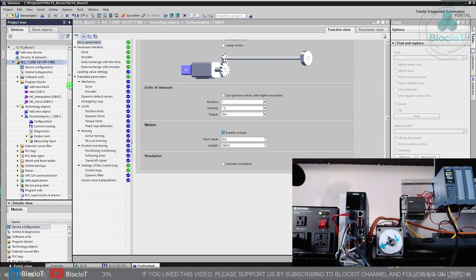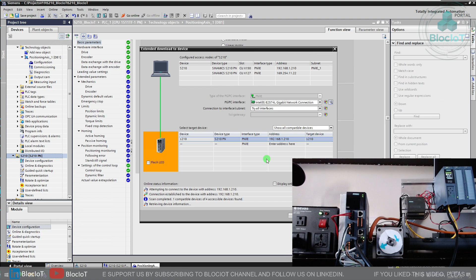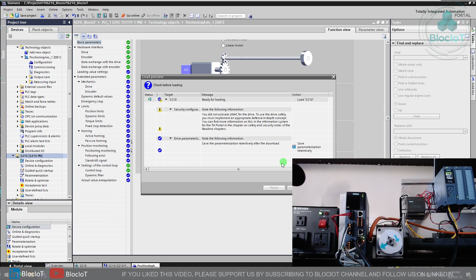After downloading your CPU, always do a download from the TIA Portal to the drive as well. Do a load, and make sure this option is checked: save parameterization retentively, because you want to save all the parameters to the drive permanently, then hit load. Now we are almost done with the drive.